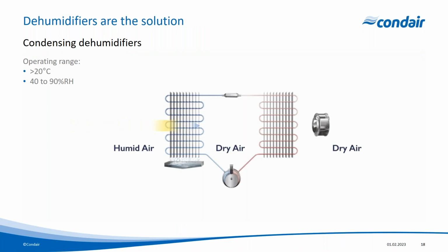So if dehumidifiers are the solution, what kind of dehumidifiers do we use? Well, when most people think of a dehumidifier, they think of a condensing dehumidifier, which is a traditional direct expansion refrigeration cycle. And most of you will recognize the schematic here. You've got a compressor, a hot gas side, there's your condenser, a pressure change device, and an evaporator where the liquid is going to evaporate. So you've got a cold coil here, and humid air comes along and hits this cold coil, and condensation occurs, and that condensation is dehumidifying.